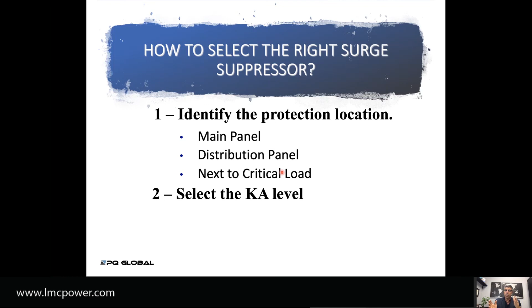The next thing you need to identify is what KA rating is required. At the main input panel it would be 150 KA or above, distribution panel 100 to 150, and next to the load 50 to about 100. Those are just rules of thumb, but like we saw in the drawings, we can be flexible and creative. Then we select the nominal voltage, whether it's 480 or 208, 120, and there you have your product.